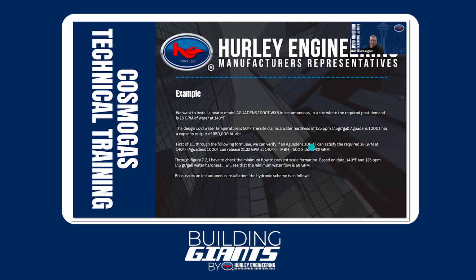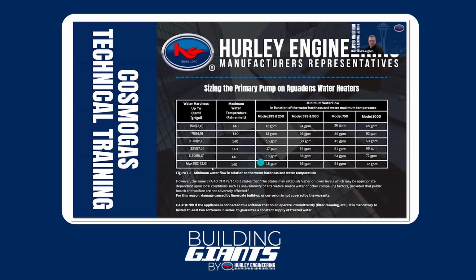Okay, so now I know that if I'm using a million BTU boiler, I'm going to go back to my chart. Million BTU boiler, 125 parts per million on my hardness. So my minimum flow rate would be 68 GPM. If I take that 68 GPM and follow it up, I've got approximately 33, 34 feet of head loss at that flow rate. Now keep in mind, that's a minimum. If you get a pump that does just 68, we're always going to size it a little bit over, because we don't want to be sized for the bare minimum.